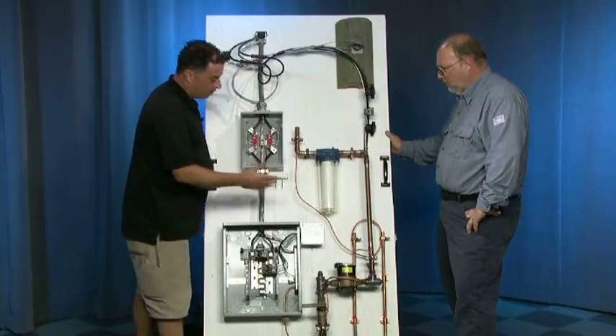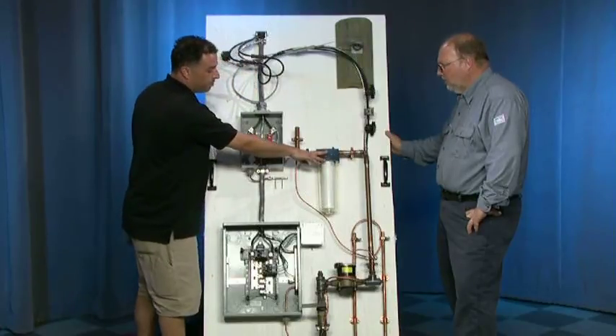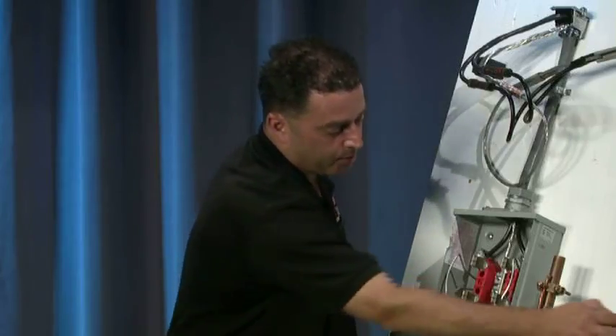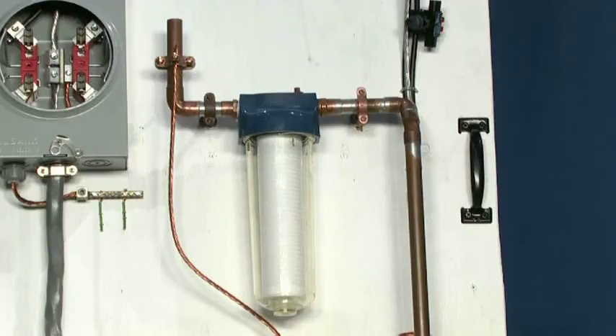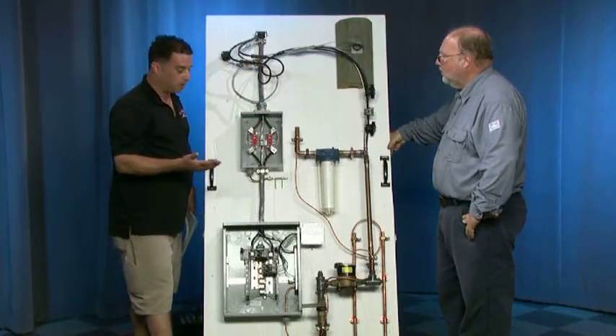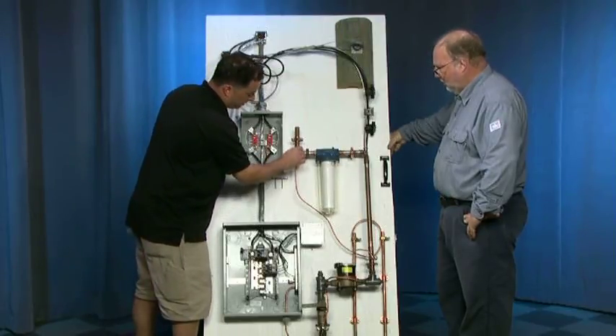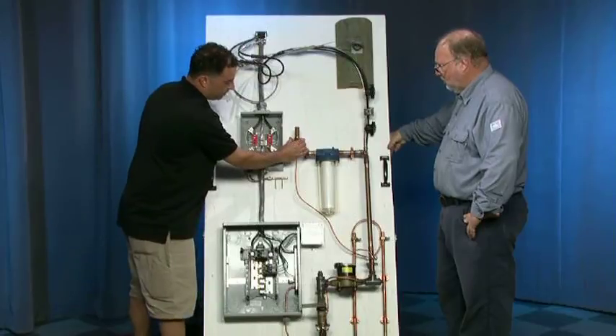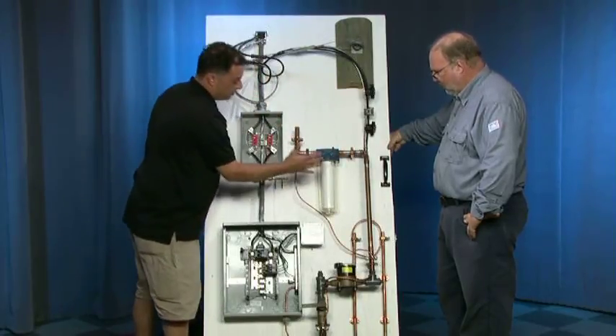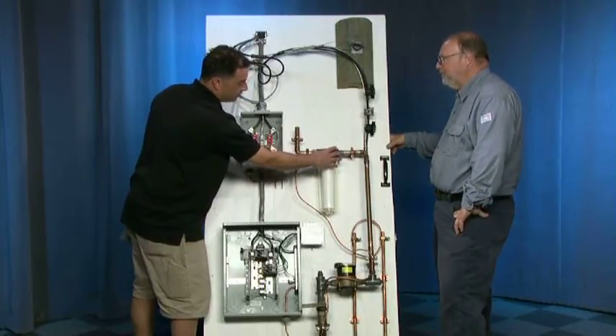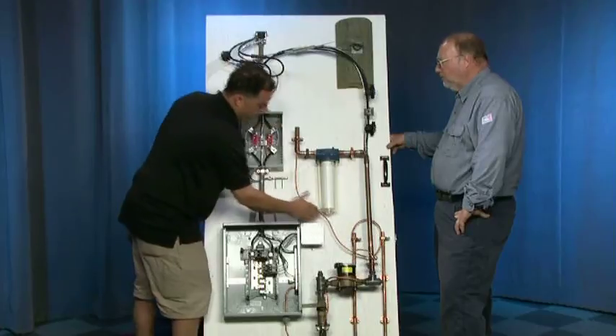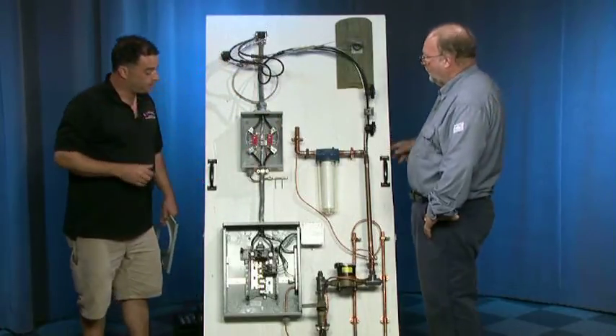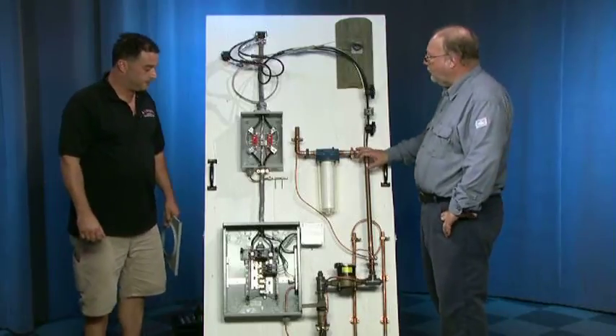Most houses, some, not all, have whole house water filtration systems. They tend to be plastic. So by intercepting this copper pipe and installing a plastic water filtration system, you've actually taken away the ground that grounds your spigots, your faucets, and your water piping system in your house. So what is very important is that this is also jumped out. So we have a ground clamp on this side, and we have another ground clamp on this side. So if somebody was to come in and replace this or remove it, you're still maintaining your continuity of ground to your house. Yep. And a couple problems that we see out there is, not to pick on the siding guys, but they come to your house, they side, and they leave all this floating off the house.